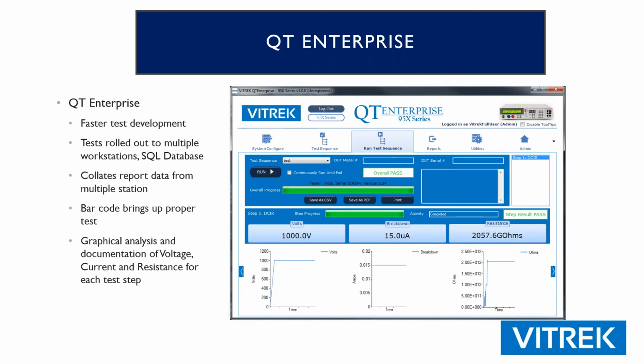So the benefit here is it's going to allow you to quickly develop a test. It's a graphical interface. You can check boxes to close relays, save all of those different test sequences, and then everything can be exported. So you have the ability to serialize each thing, store data, graphically look at what's going on during your test, and then apply those pass-fail limits during the test.